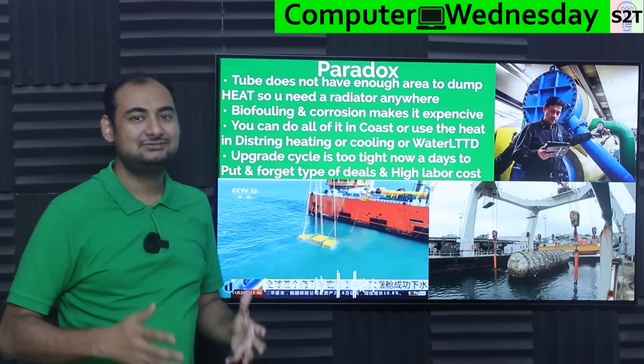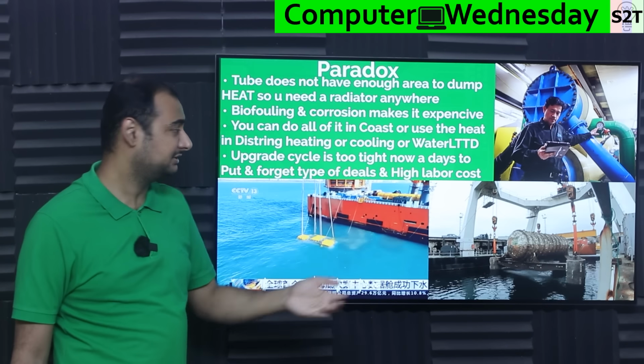If you have that much heat, it can be supported with district heating. If some European grid is already burning megawatts of heat for district heating, why not couple these two? Everybody wins. Another aspect: what if you're doing it in India or somewhere with a cooling requirement? Cool, you still get cooling, though of course it won't be as efficient. Best case scenario, COP would be very low, like 0.25. But if you have tens of megawatts and cooling load is only 2-3 megawatts, that's at least 2-3 megawatts of cooling load removed from the electrical grid. That is useful utilization of waste heat. So you can get heating at perfect efficiency, cooling at decent efficiency, or in the case of India, where you don't have district heating, you can make water out of it.